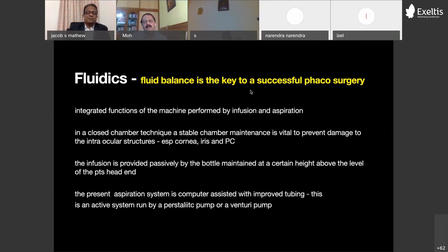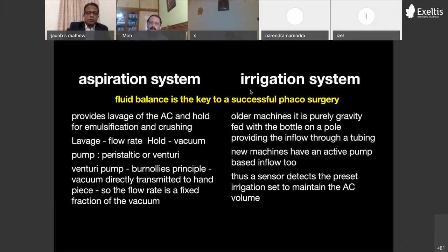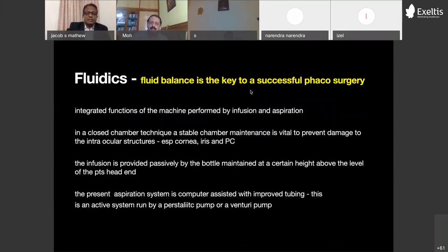So the present generation machines make sure the anterior chamber is maintained so beautifully that you don't really need to worry about all these issues, because the fluidics is so good, and quite a few machines are there on the market at the top end, and all of them are very good and highly efficient. And also the aspiration is controlled by two kinds of pumps. One is the peristaltic pump, where tubing goes around a cassette where the wheels milk the fluid in the tube, and that causes a negative pressure which is transferred to the tip of the probe, and that's how the vacuum develops.